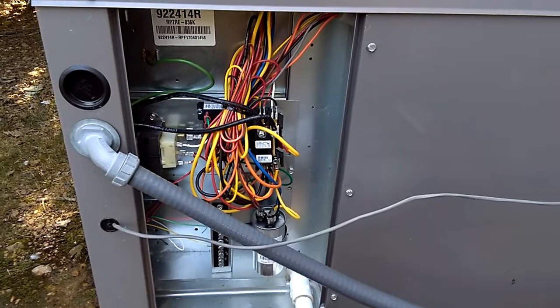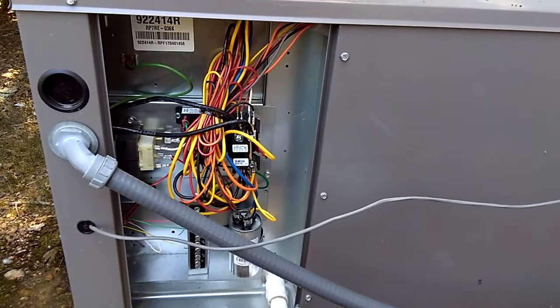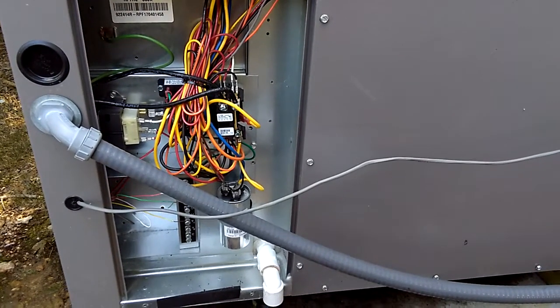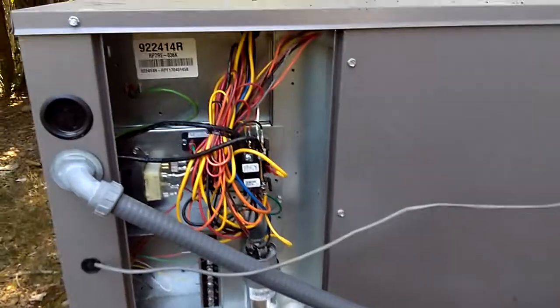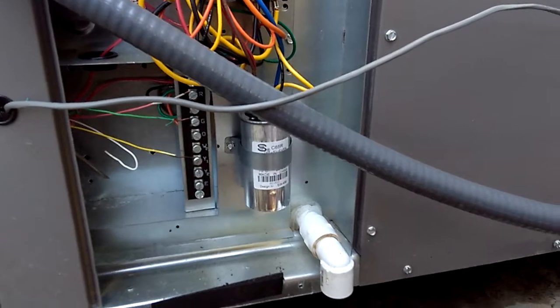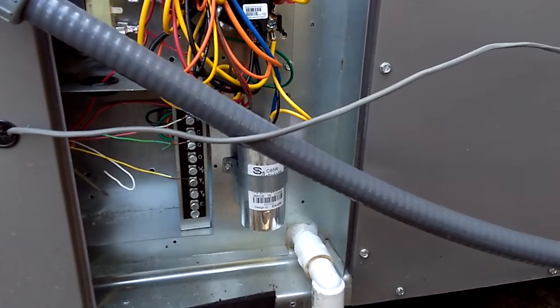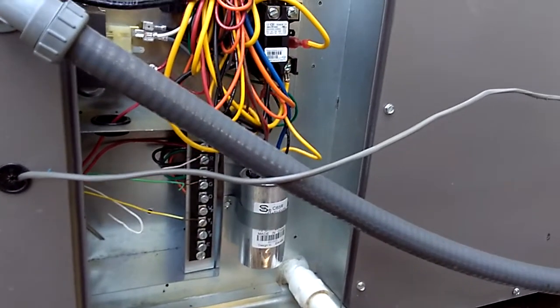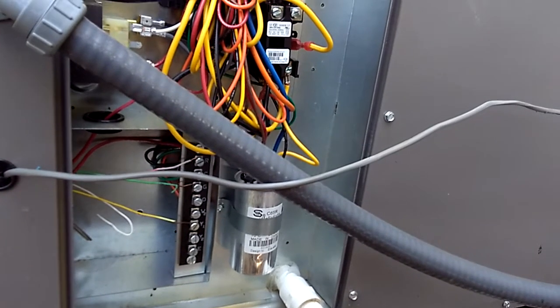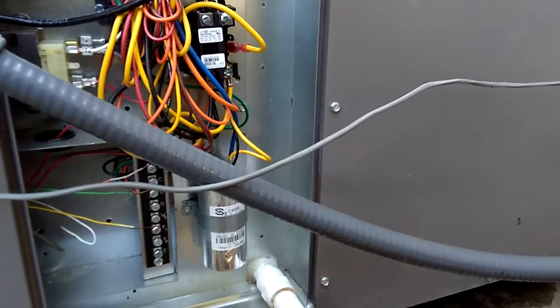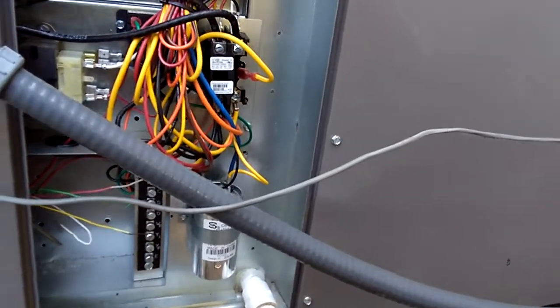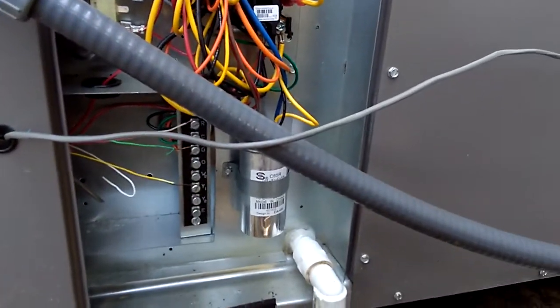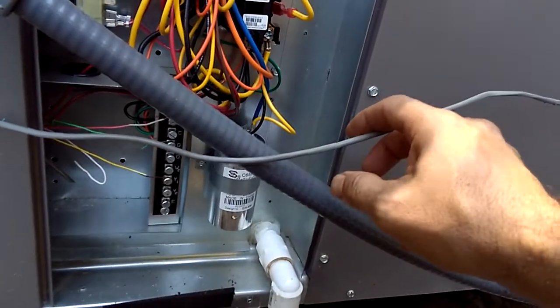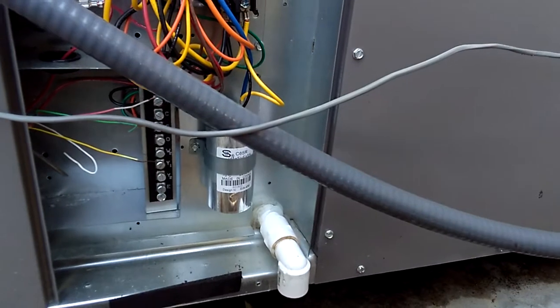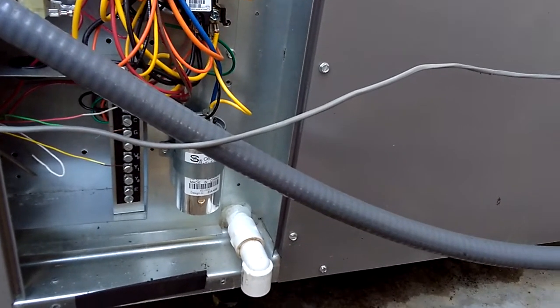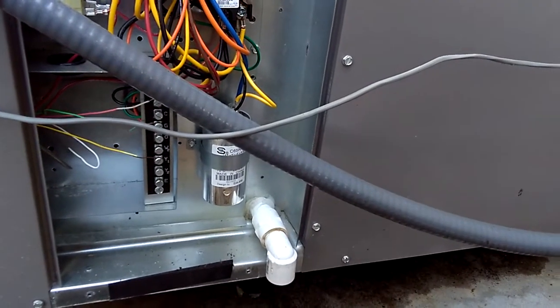So basically I'm just hooking up the thermostat wires, because it's the same as the previous unit I had in. The thermostat wires would be the same. There are 3 thermostat wires: a red one, a green one, and a yellow one. It's a 24-volt thermostat setup. It has a little transformer in there, but all the consumer has to do is hook up those 3 wires that come from the house. You've got a red one, a green one, and a yellow one. But this is just for air. There's no heat strip and there's no heat pump on this one. So I've just got the 3 wires.